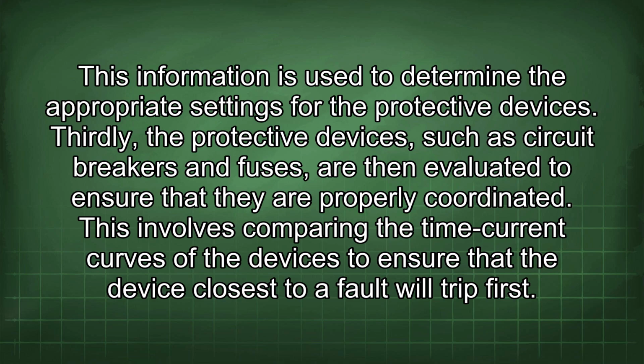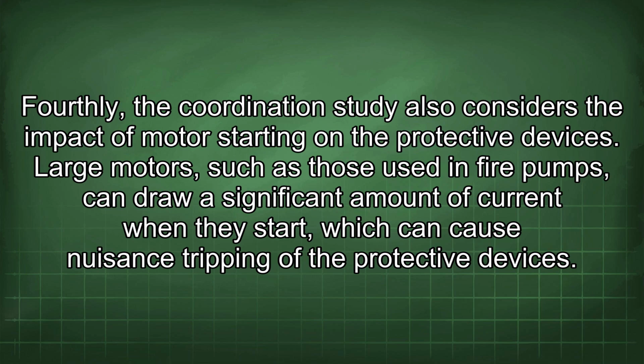Thirdly, the protective devices, such as circuit breakers and fuses, are then evaluated to ensure that they are properly coordinated. This involves comparing the time current curves of the devices to ensure that the device closest to a fault will trip first. Fourthly, the coordination study also considers the impact of motor starting on the protective devices. Large motors, such as those used in fire pumps, can draw a significant amount of current when they start, which can cause nuisance tripping of the protective devices.